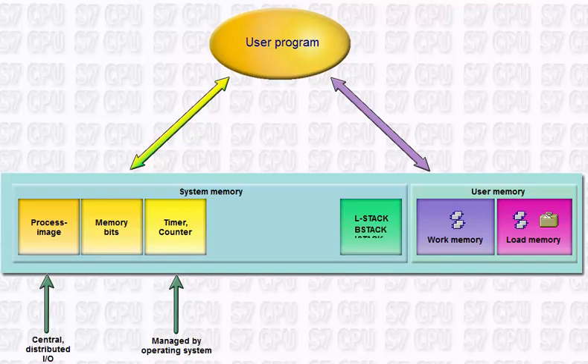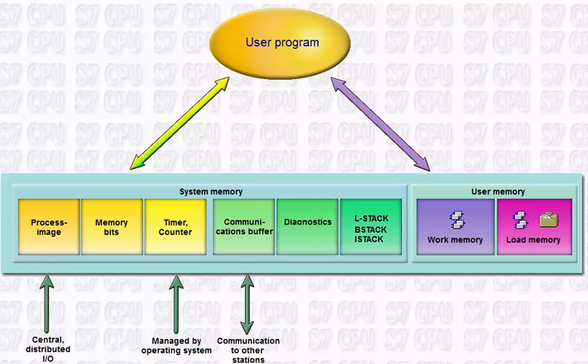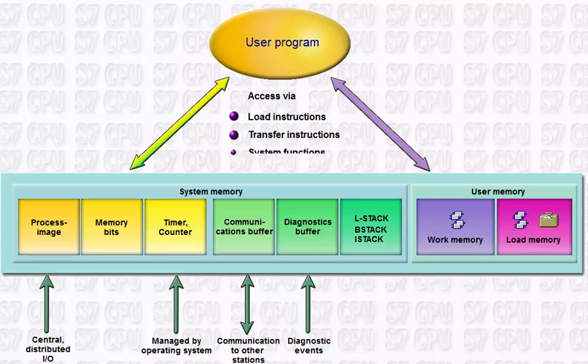The block stack and the interrupt stack are used for internal management of the call hierarchy. For diagnostics purposes, they are only accessible in stop mode. Additionally, the system memory contains buffers for communication jobs to other stations and system message buffers for all of the diagnostics events of this station. The classification of memory areas and access methods by the user program is independent of the selected programming language or the CPU type.